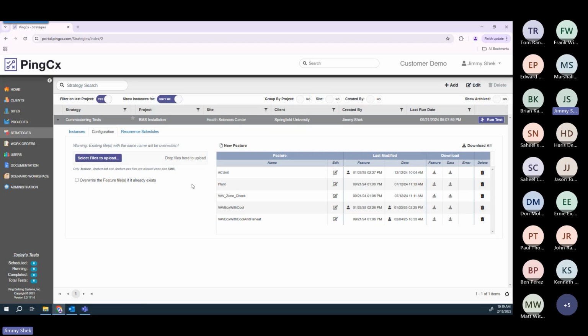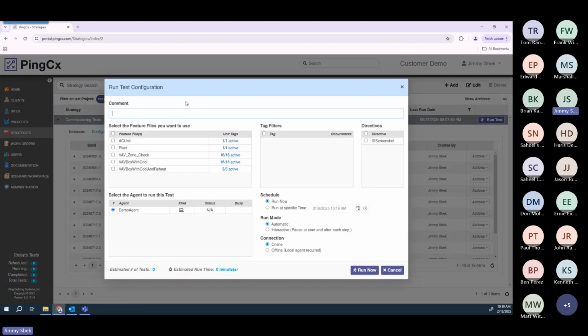Once those feature files are created or uploaded, you can use the schedule here to schedule a job. On the schedule screen, you have the ability to select which feature files you want to be included in this particular run, as well as the tag filters. Typically, the tag filters are tagged per test scenario. So early on in the testing and commissioning process, you may only want to be running the point-to-point checks, where the test scenarios are just making sure that the sensors are reading properly. And then later move on to more functional tests, where those test scenarios are opening dampers, enabling fans, checking confirmation, end switches, etc. And then lastly, moving on to the more sequence-related test cases, where those test scenarios are actually testing the sequences/strategies that are programmed on the controller.